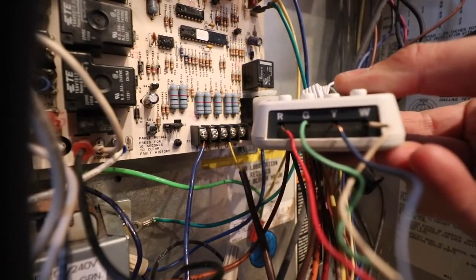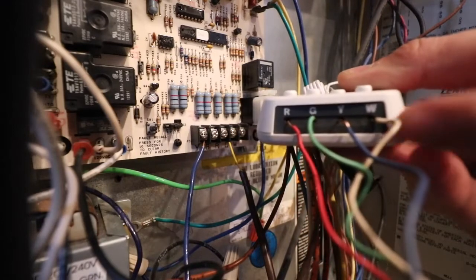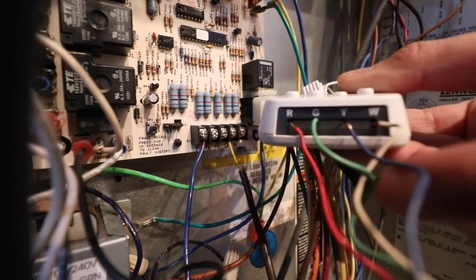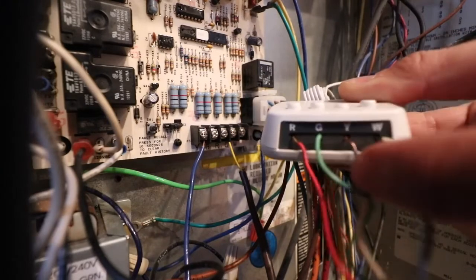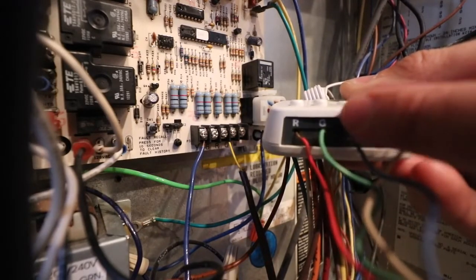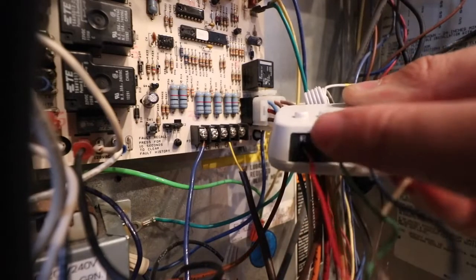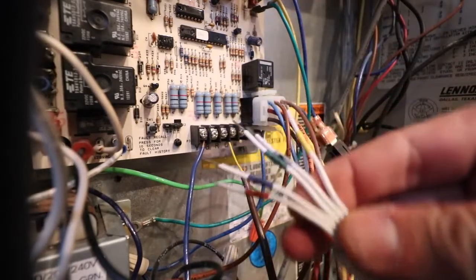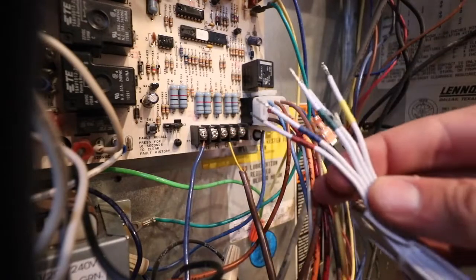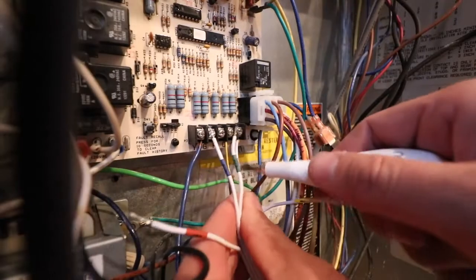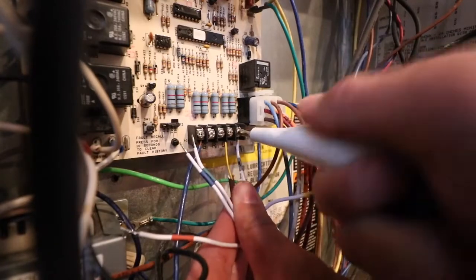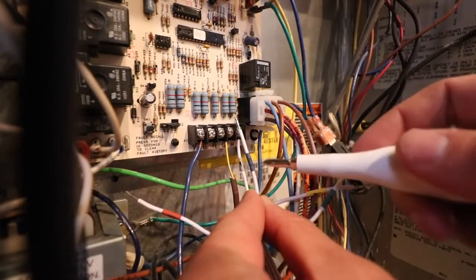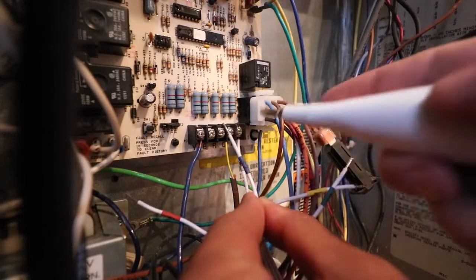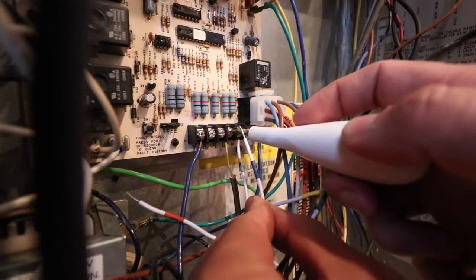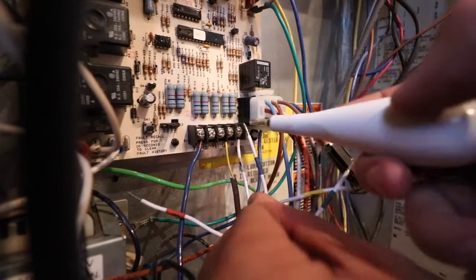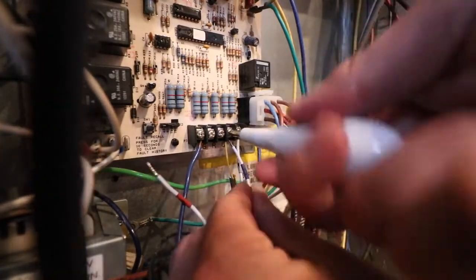So we've got all the wires installed on the adapter: the white wire, W wire in W, the blue wire, the Y wire in the Y terminal, the G wire, the G terminal, and the R wire or red wire in the R terminal. Now we've got the wires here to connect to the circuit board, so we're going to go ahead and do that. We connect the W wire to the W terminal on the control board. We then take our C wire, which is the common wire, and we connect it to the C terminal on the control board, which already has this existing yellow wire also that goes up to our air conditioning compressor.